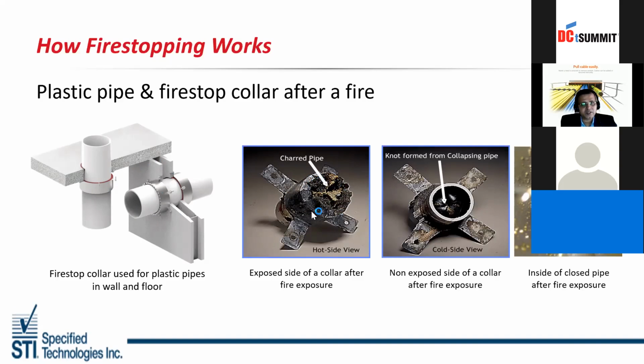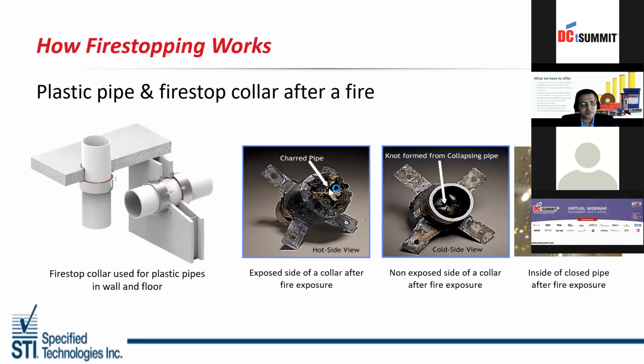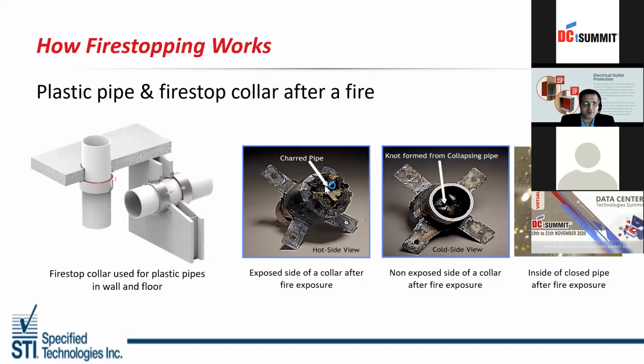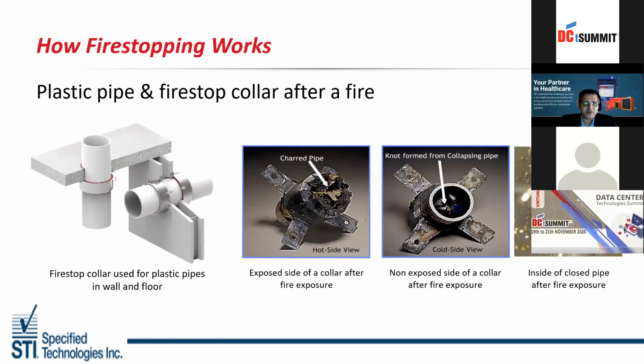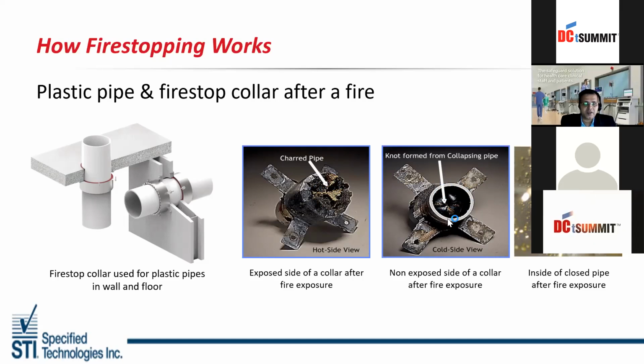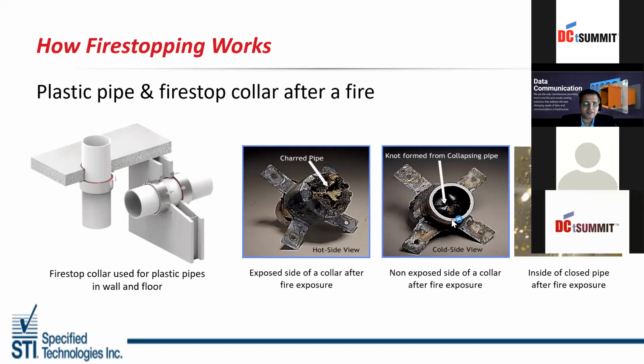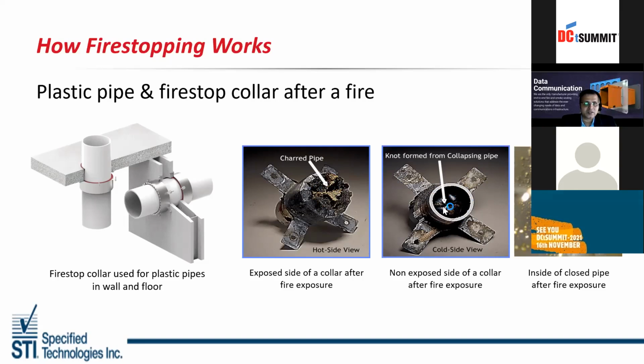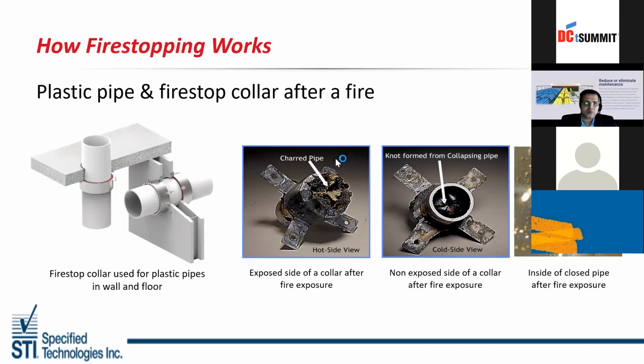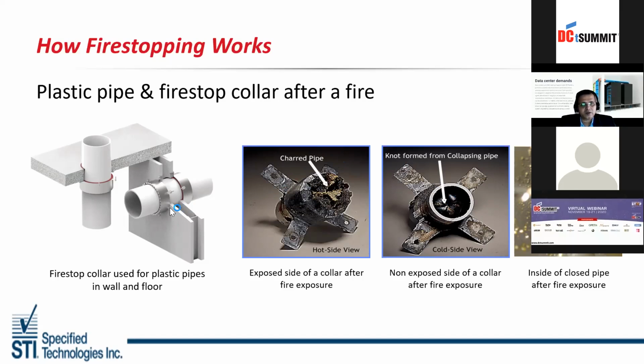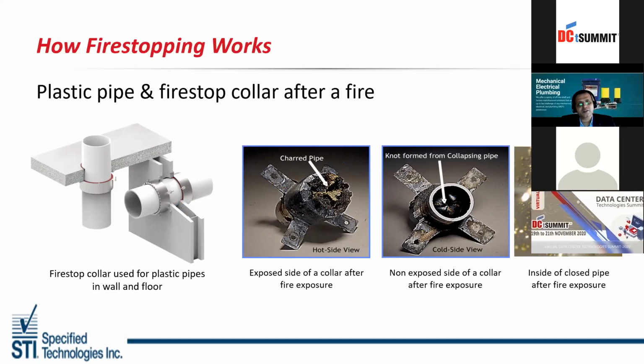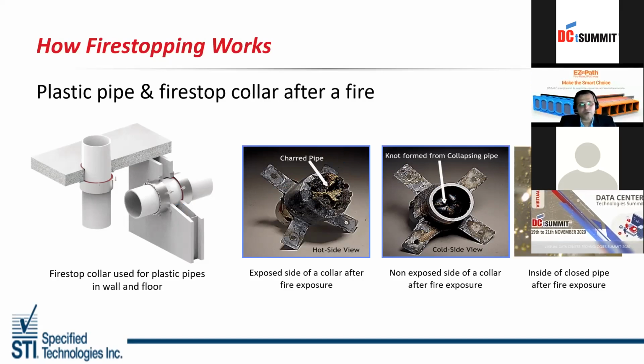The pipe has been tested. The pipe where the fire has happened, you can see the charred portion. The intumescent product has expanded, the collar has expanded, and it has stopped the fire and smoke traveling upwards. This is the other side where no fire has traveled, so you can see the pipe as it is. Okay, you can see the inside part is completely crushed. So this is the technology of intumescent. The product is crushed and stops the fire and smoke traveling to the other floors or the other wall.